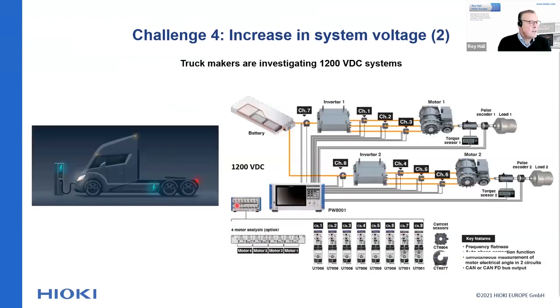Another situation where we see an increase of the system voltage is the development of electrical buses and trucks. The general EV cars on the market are using at this moment a 400 or an 800 volt bus system. But now when we are looking into the trucks, more power is required, and therefore truck makers are looking at 1200 volt DC as a battery voltage. To be able to manage this, we have here an example of a dual drivetrain power system. You have to be able to measure the DC of 1200 volts accurately and according to the standards.